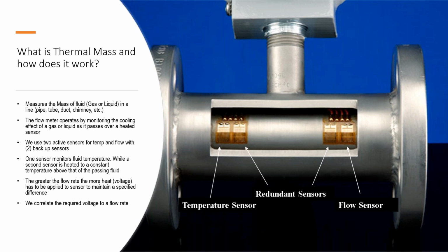We use basically a two-sensor approach with backup sensors that are ready to go if necessary. We have one sensor that measures the fluid temp, and then it sets the temperature of a second sensor, the flow sensor that you can see in the picture here. It sets that second sensor to a predetermined and constant temperature above that of the fluid passing by. So basically, as we tie a voltage to that sensor, and as more fluid goes through that unit, we actually have to increase the voltage to maintain that constant temperature differential.